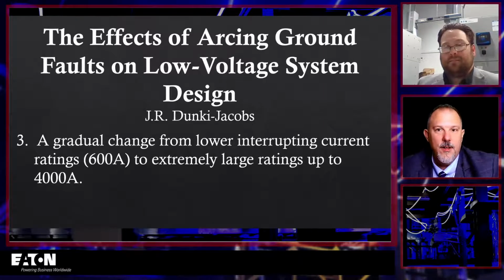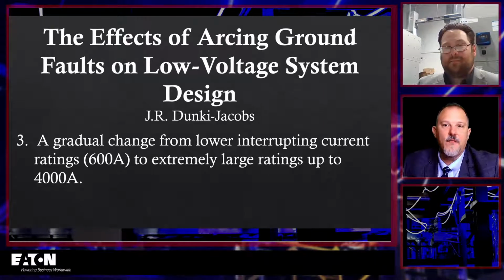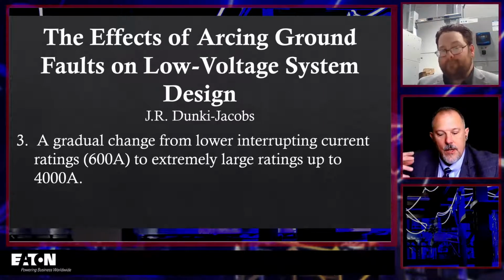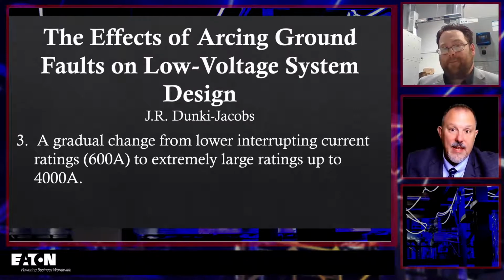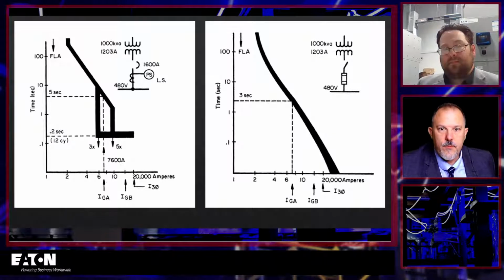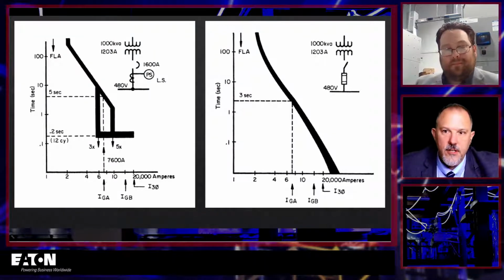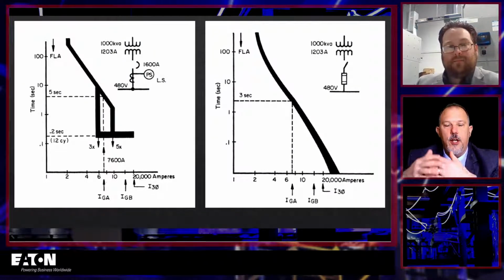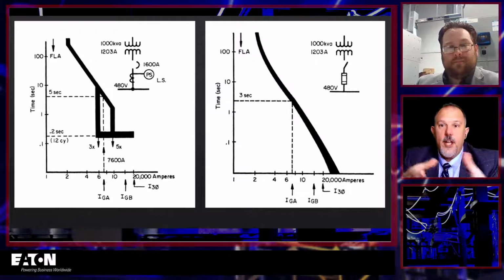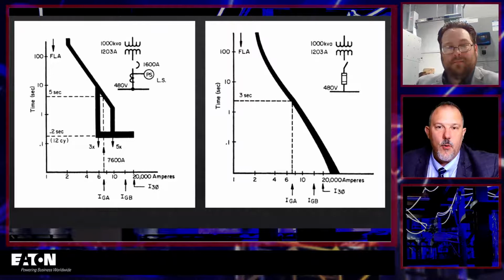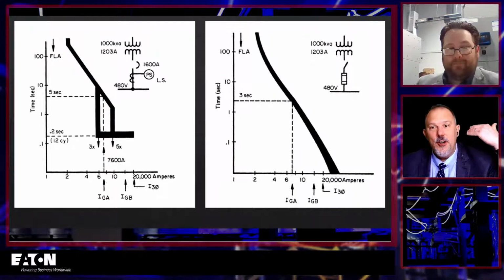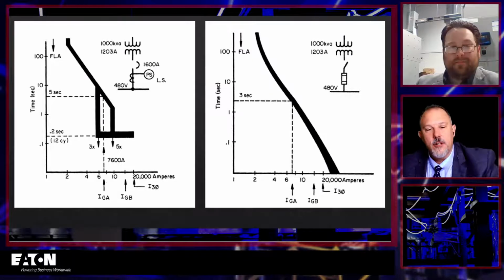And what do we know that does that? Arc flash events, right? So when you look at this, and then you look through Dunki-Jacobs' papers, you have these large overcurrent devices, which you have your arcing ground fault currents, your arcing currents, which we know now 1584 will let us calculate an arcing current. And we know that those lower arcing currents give us longer clearing times.